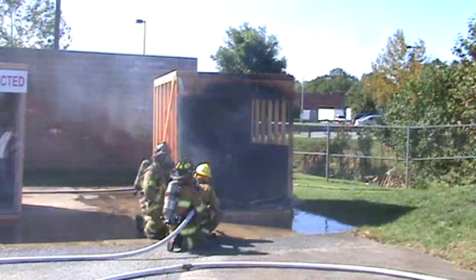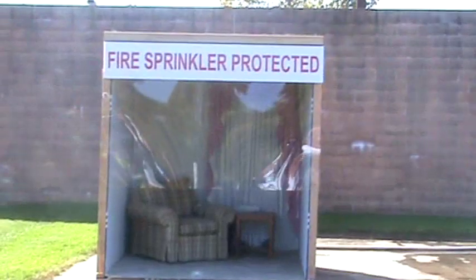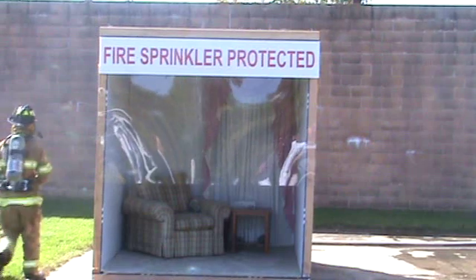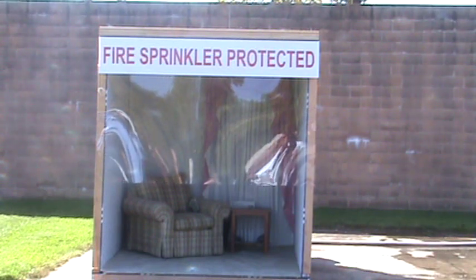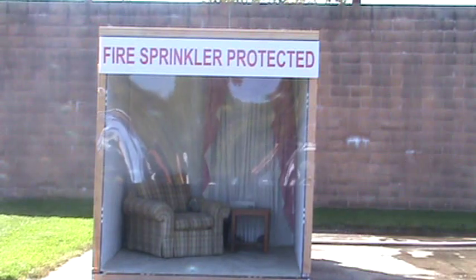Are we ready to start the second demonstration? The other cube that we have here is, again, eight-by-eight. It's been constructed identical to the room you just saw, and the fire is going to start in a very similar manner — in the wastebasket with the curtains. The rooms have been furnished as identically as possible. The difference in this room is that it is equipped with an automatic residential fire sprinkler, which is typically going to activate at about 150 degrees.